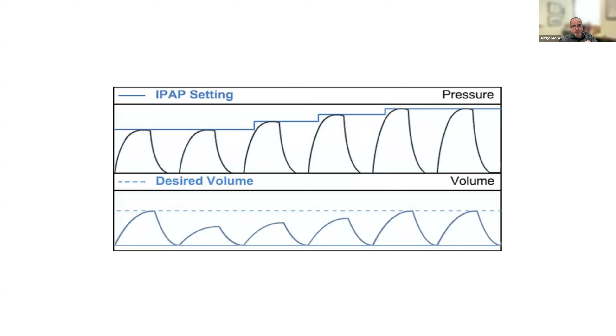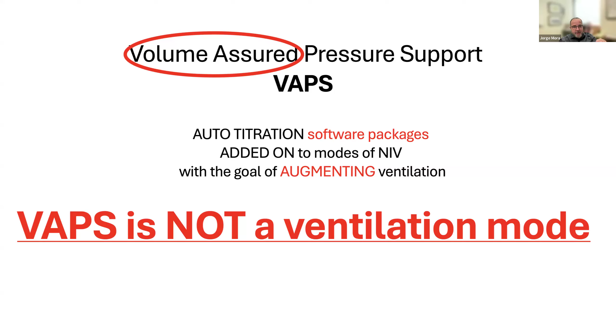I want to remind you that AVAPS, whatever variations of these, AVAPS, iVAPS, whatever you want to call it, is not a ventilation mode. This is still bi-level. This is still pressure support. It's just that it has a very specific algorithm that allows for adapting and targeting a volume. You can do many things on these devices. I'm not going to go into details. They have an integrated auto CPAP, if you want to call it that way. You can play with these TE min and TI max.